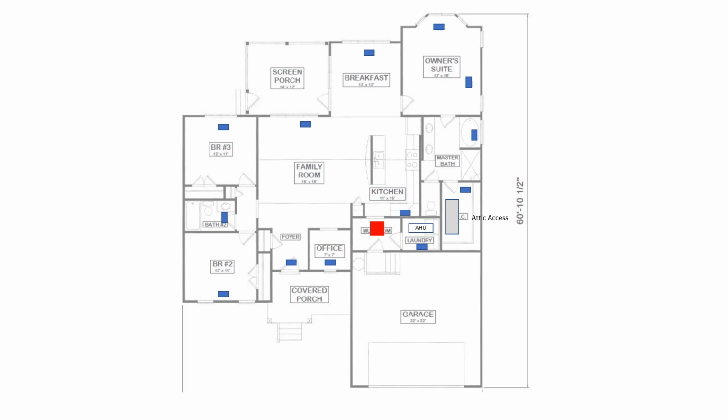Let's imagine what happens to the bedrooms when the doors close. Typically this happens at night. If there are no returns in these rooms, that means we're supplying air to these rooms and building pressure in them. Now that air wants to escape these rooms and it has very few paths out. Usually door undercuts are not large enough to relieve that pressure and allow enough air out. This is especially true in the master suite because there is a bathroom and several closets behind that door as well. So in this case, it totals 4 supplies. All that air wants to escape somehow, and it will take all paths, including the small gaps and seams in the building envelope, and exfiltrate out.